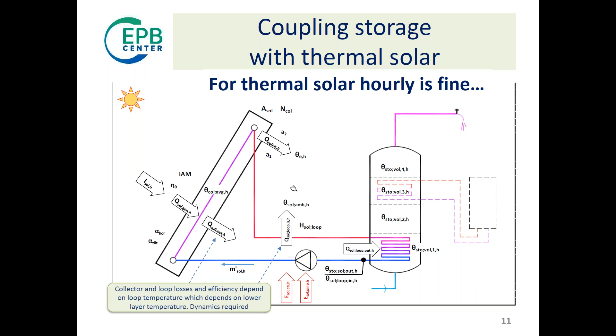There's another possibility: with the hourly method you can remove one of the assumptions. The monthly calculation assumes everything is working fine at every time. With an hourly calculation, you may identify that you are overheating your collector — if you reach 90 degrees, there's a lockout, and you have to wait until the collector cools down again. This can be identified with an hourly calculation, not with a monthly one that assumes everything is working well — just the opposite of Murphy's law, as you may know.